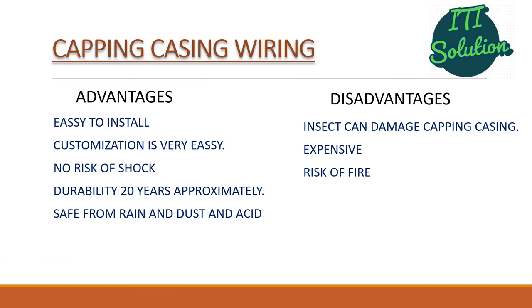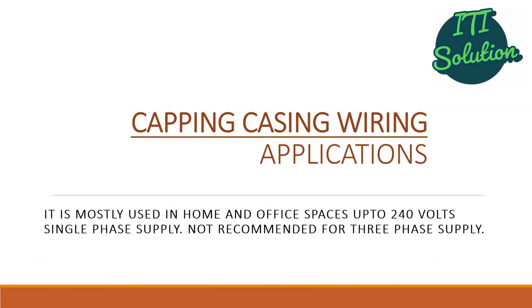Advantages of capping casing wiring are easy to install, customization is very easy, no risk of shock, durability of approximately 20 years, and safe from rain, dust, acid, etc. Disadvantages include insects can damage capping casing, it is expensive, and there is risk of fire. It is mostly used in homes and office spaces up to 240 volts single phase supply and is not recommended for three phase supply.